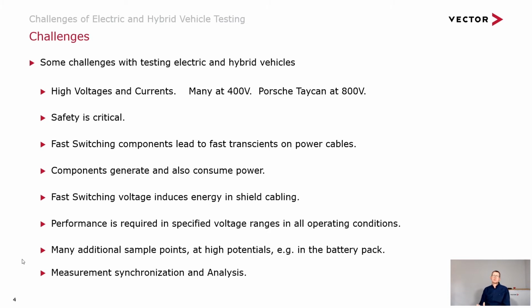And then finally, measurement, synchronization and analysis. If we've got a lot of fast transients, then we need a lot of equipment to measure all of those transients, and we have a challenge of how do we synchronize all that data. And if we are measuring voltage and current into the inverter and out of the inverter, that could be 8 signals, that could be 8 mega samples per second. And then if we're doing additional online analysis, then there's a lot of data being generated and saved. So is our equipment up to the task?